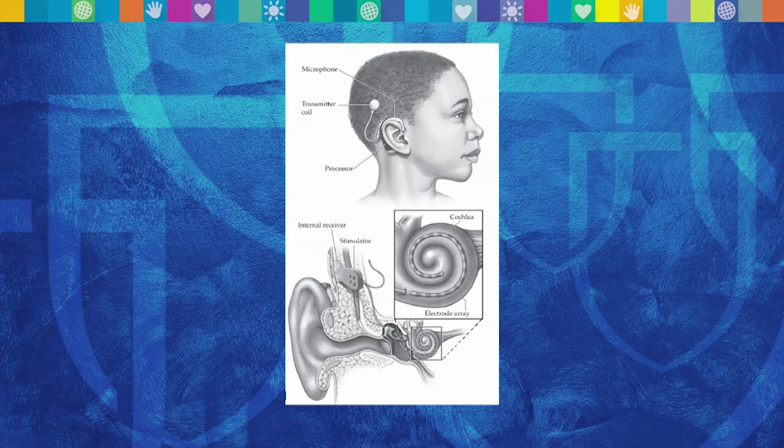There's different models, you might say. So the most typical structure that people will see if you look up cochlear implant, there's a device that looks like a behind-the-ear hearing aid, a large version of that, and it has a separate wire with a round, what we call coil. So in that device behind the ear is a microphone. It picks up sound, it processes the sound, it sends it down the wire to that coil, and then across the skin, a radio signal is sent to the internal device. So there's a part we put in surgery underneath that. And that information is then decoded, really, or processed further in the internal device. It's sent down a wire that we've threaded into the cochlea, into the inner ear, and then we directly electrically stimulate the hearing nerve. And essentially, we're bypassing a lot of the parts of the inner ear, the inner hair cells, the outer hair cells, and some of the other things. We're going straight to the nerve.